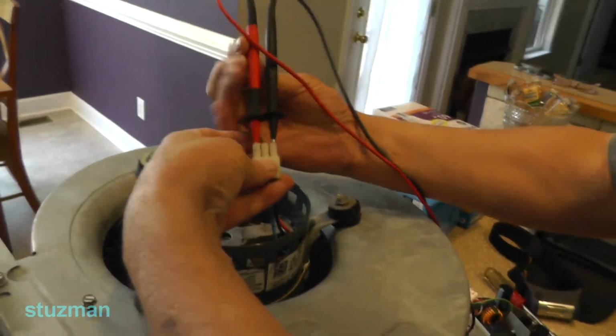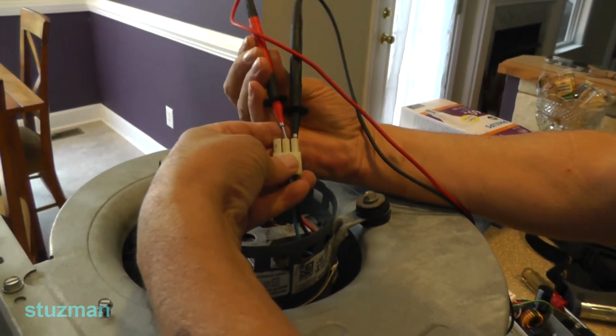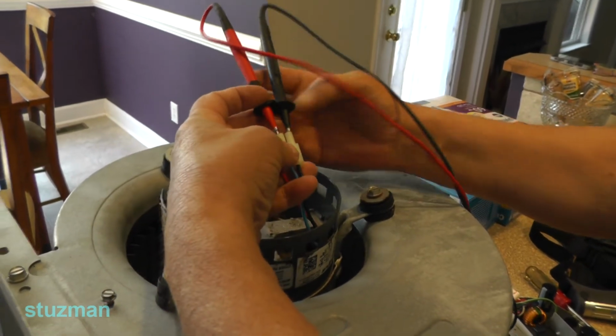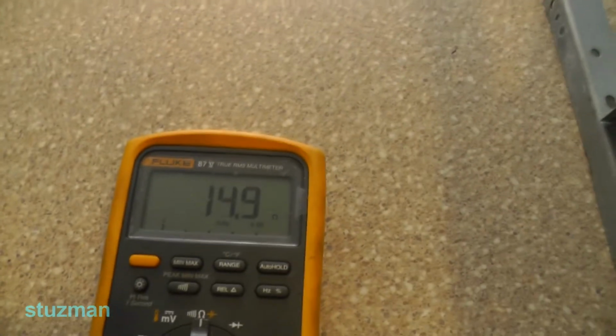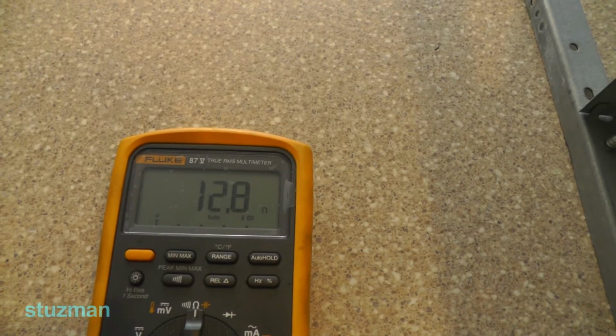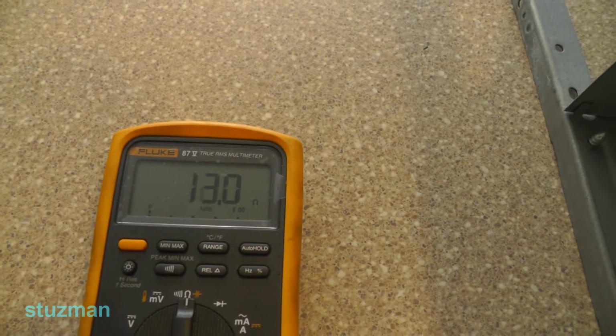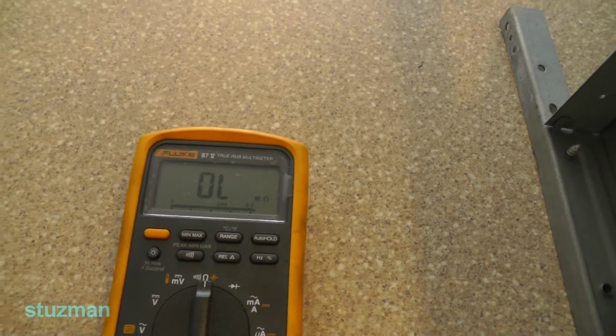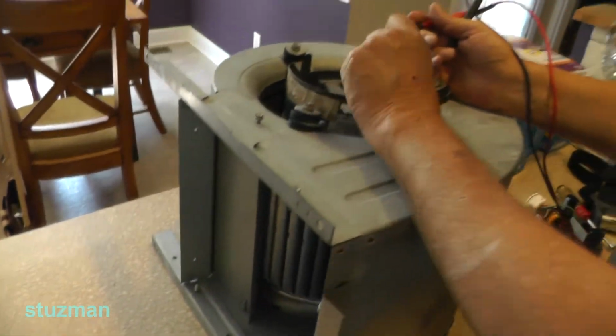Now I'm going to take this lead and move it over here. That's all 3 possible checks on all the windings. There you go, that's 13 ohms - that looks good. Remember, you want your readings to be plus or minus 10% of each other.